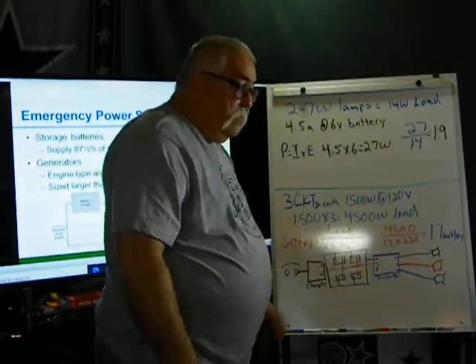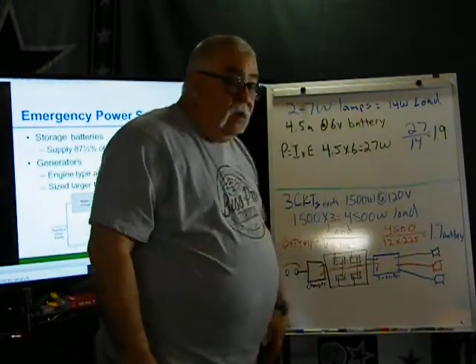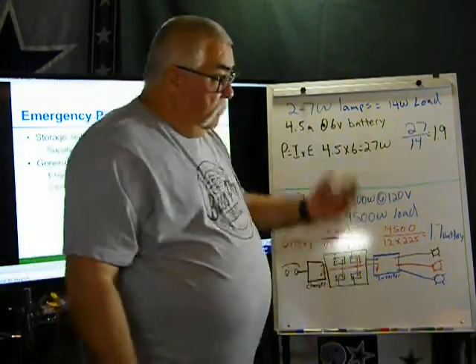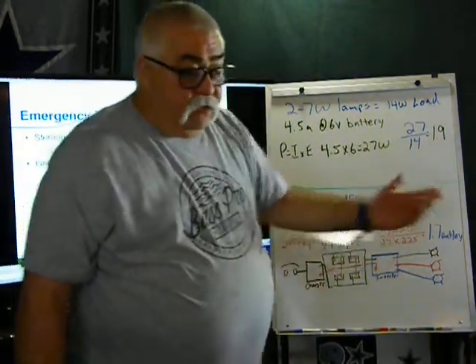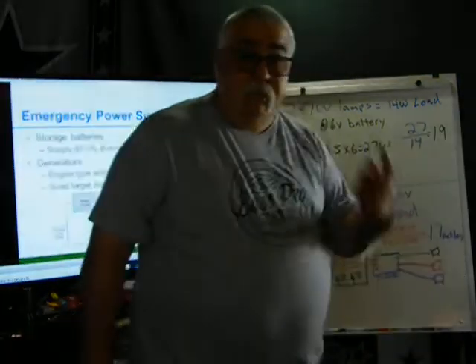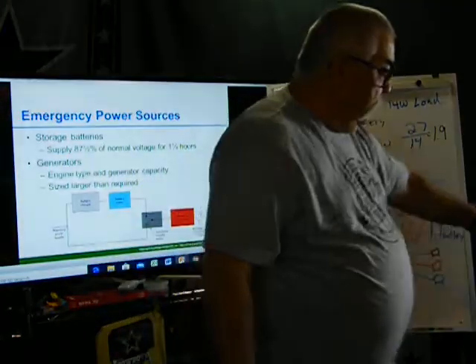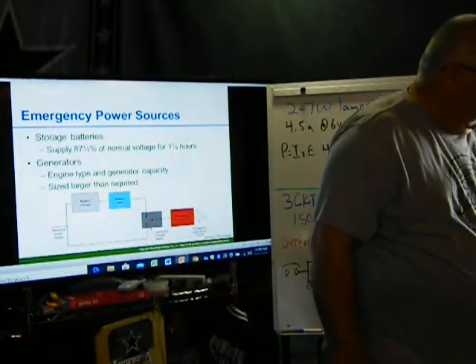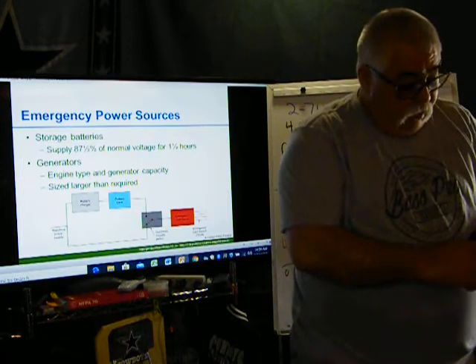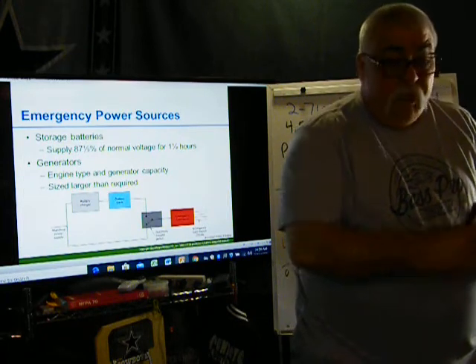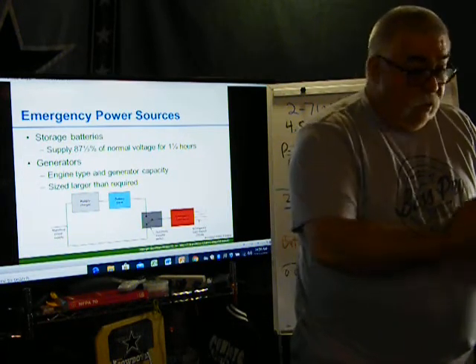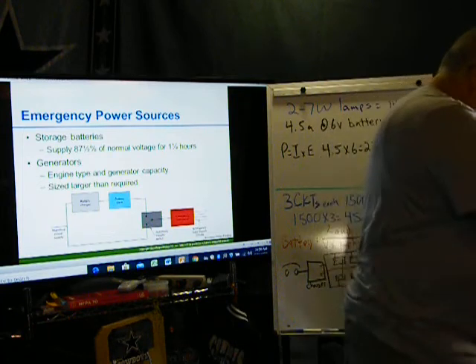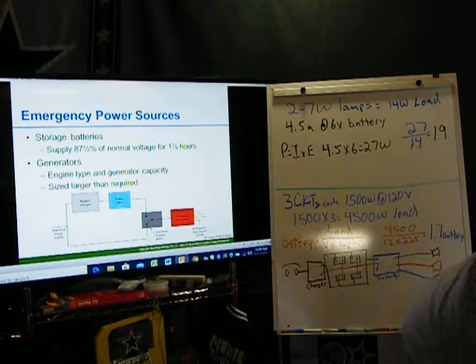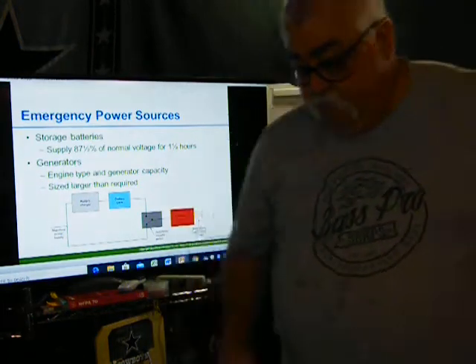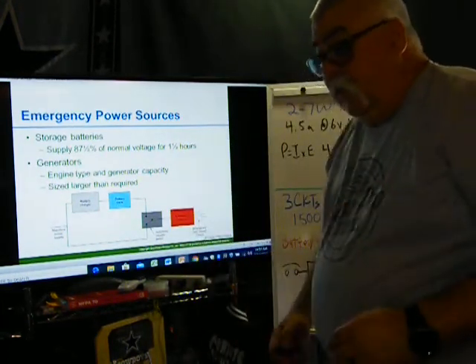So always remember, turn power off. It's got to stay on for an hour and a half. If it doesn't stay on for an hour and a half, you either have to change batteries or change the lights. Okay, you also have to test them to make sure the light bulbs are working. These light bulbs can burn out. These aren't LED. So these light bulbs can go bad. What do you have to do? You have to go replace them. It's all part of the maintenance to stay within the requirements of the NEC. Okay, all this stuff has to be tested.